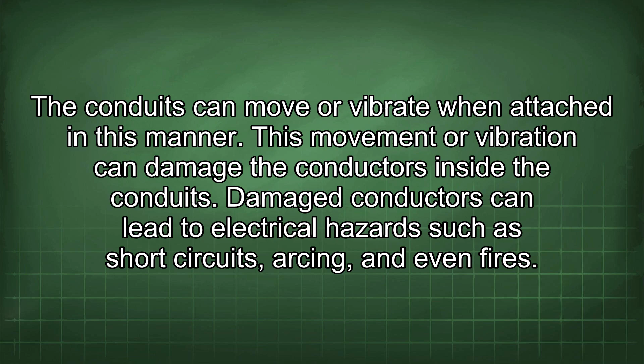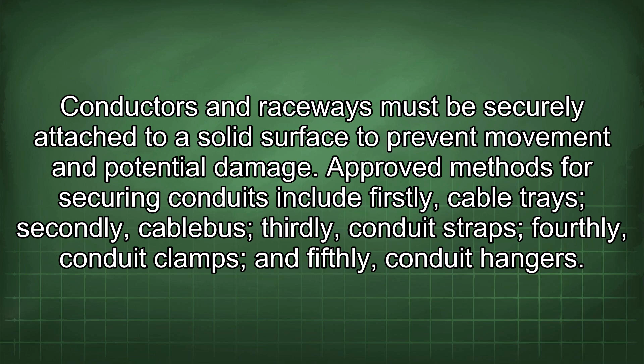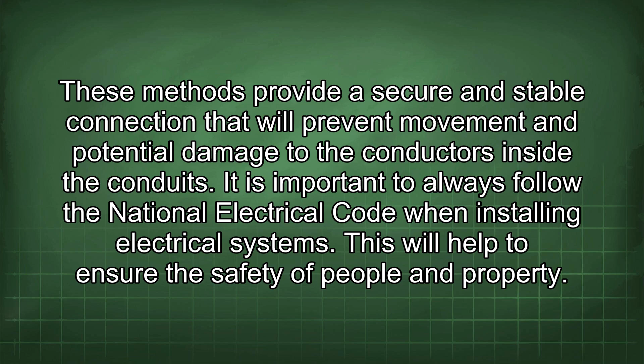Approved methods for securing conduits include, firstly, cable trays; secondly, cable bus; thirdly, conduit straps; fourthly, conduit clamps; and fifthly, conduit hangers. These methods provide a secure and stable connection that will prevent movement and potential damage to the conductors inside the conduits. It is important to always follow the National Electrical Code when installing electrical systems. This will help to ensure the safety of people and property.